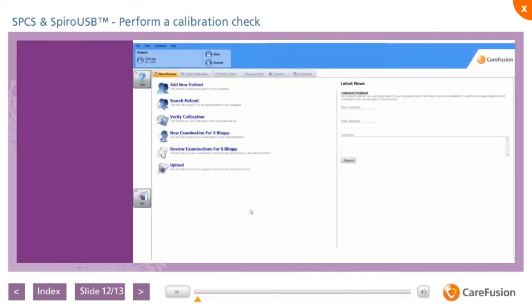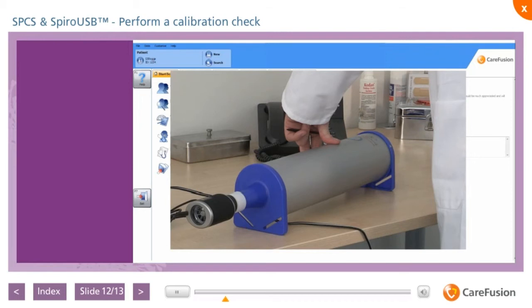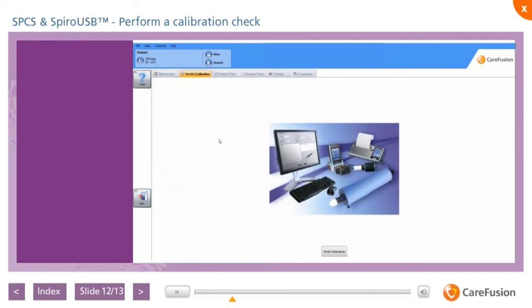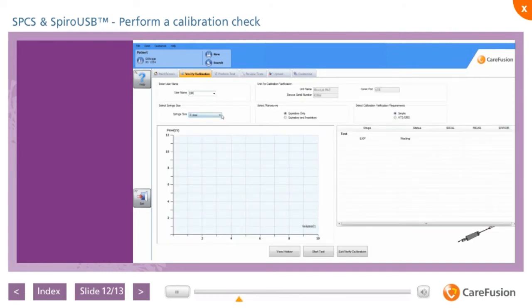The current ATS-ERS guidelines recommend that spirometry calibration checks are performed on a daily basis using a 3-litre syringe. It's important that records are kept of calibration checks performed on the spirometer, including the date, spirometer serial number, and the pass value. Connect the syringe adapter to the syringe and connect the spirometer transducer and housing as shown in the picture. Upon choosing calibration verification, the user should enter their name and using the drop-down list choose the size of the calibration syringe they're using.